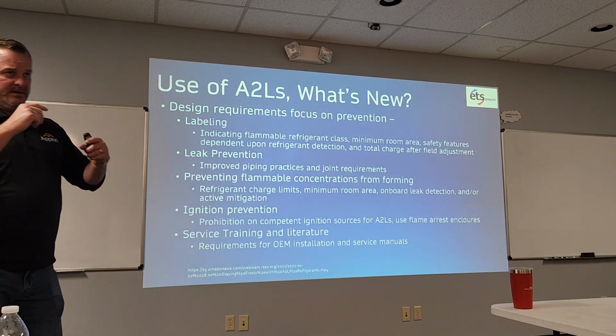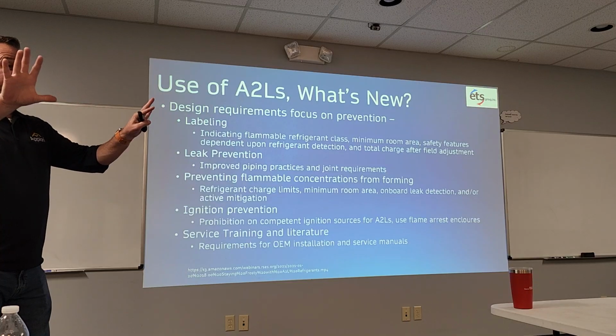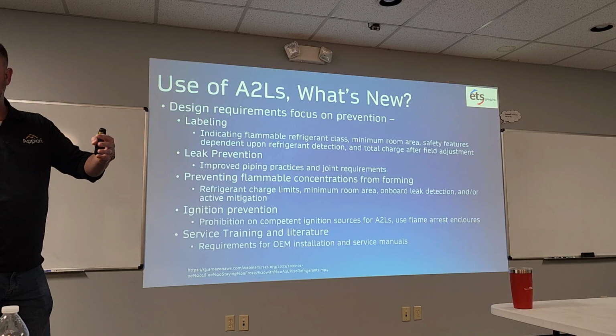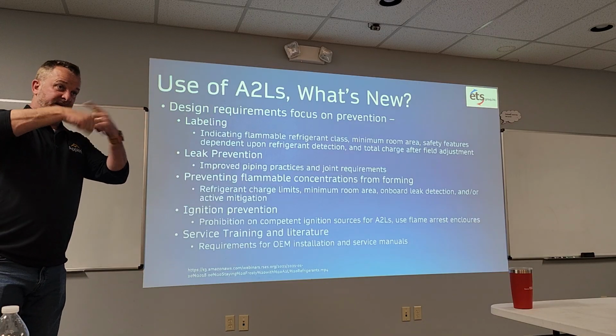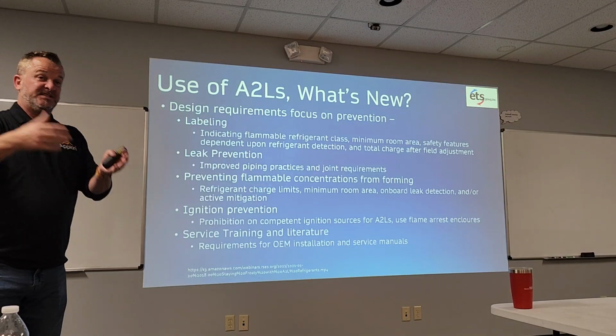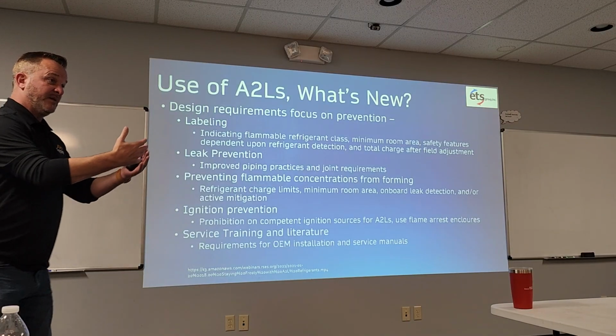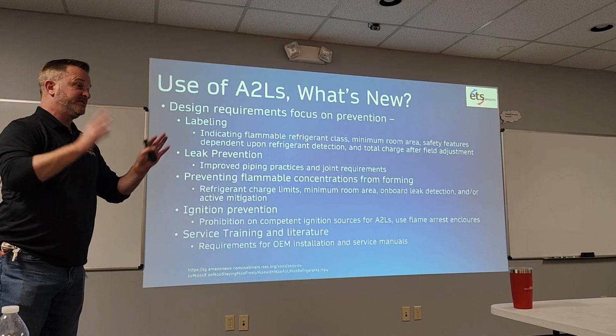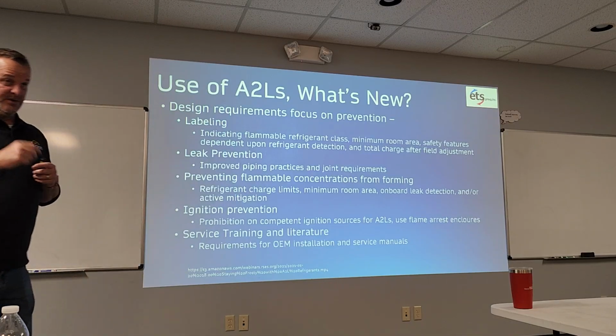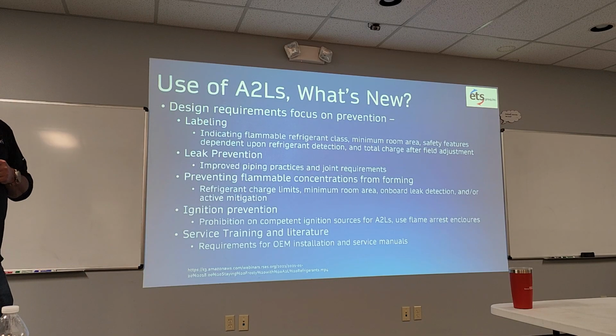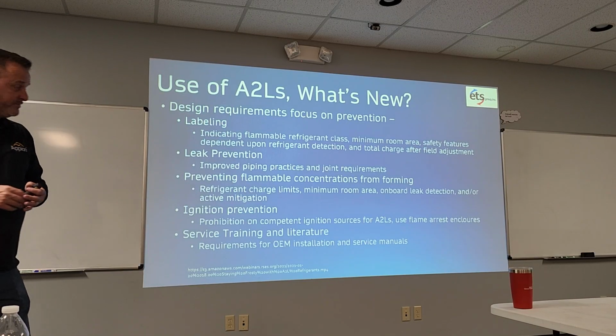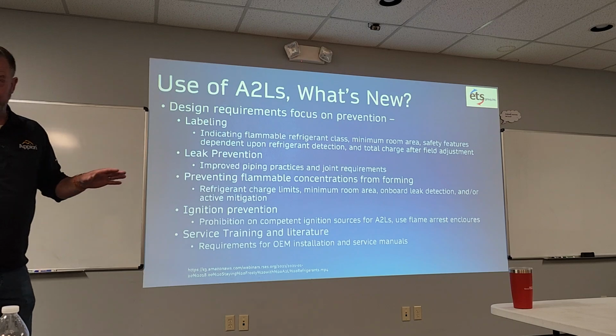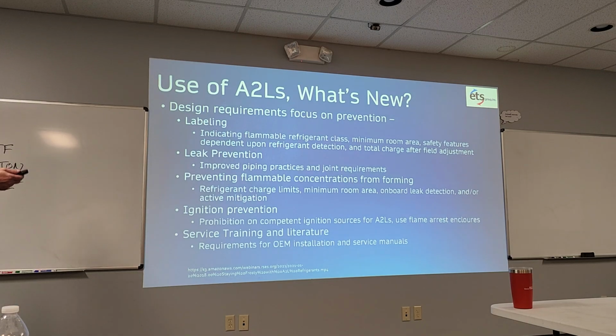So what they'll do is it'll detect the leak, it'll shut down the cycle, whatever the cycle is, whether you're in heating mode or whatever, and then the blower will kick on and dissipate that refrigerant for a certain set amount of time. Then the system will kick back on and go back to normal operations, no more leak, everything's good. It'll do that up to 3 times. After the 3rd time, if it still has a leak, it's going to code out the system, and you're going to have to call a contractor to come in and work on it. Some will shut off right away. It all depends on the manufacturer. It's all pretty similar, but a little bit different.